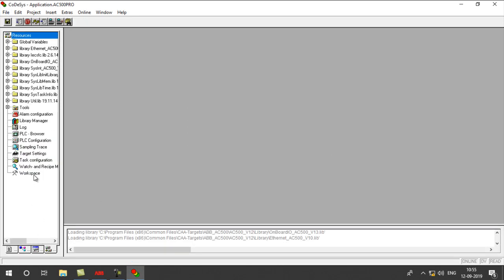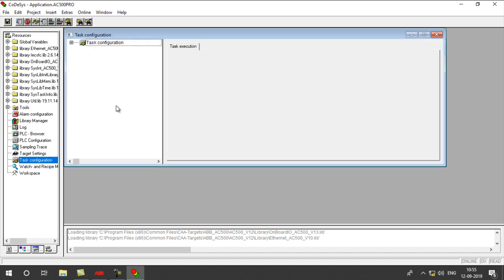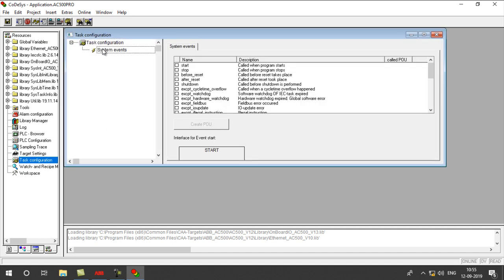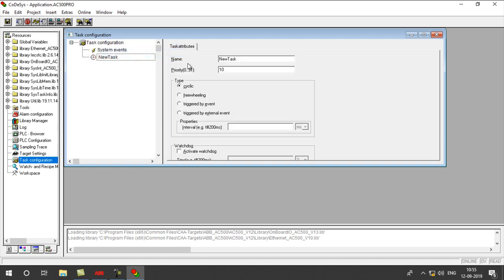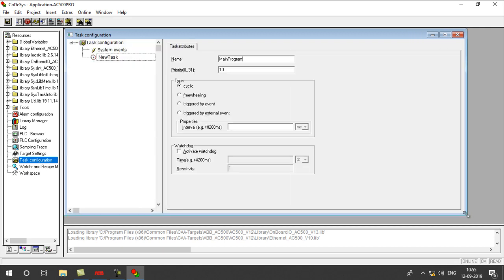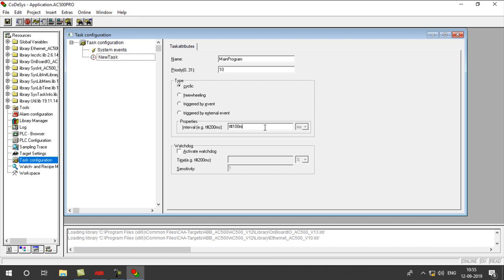In this, go to resources, double-click on Task Configuration, this page will open. Right-click on System Events, Insert Task. Name it as Main Program. And here we have to set the scan time. I am setting it as 100 milliseconds.